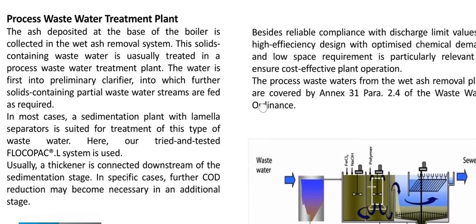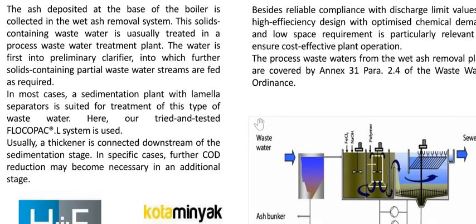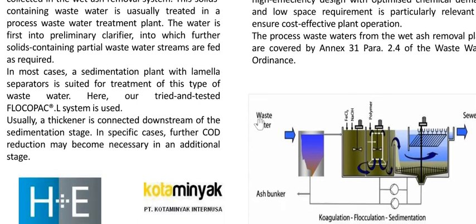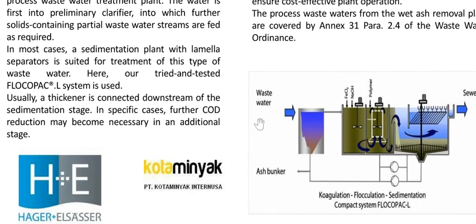Process wastewater treatment plant. The ash deposited at the base of the boiler is collected in the wet ash removal system. This solid-containing wastewater is usually treated in a process wastewater treatment plant. The water first goes into a preliminary clarifier, into which further solids-containing partial wastewater streams are fed as required. In most cases, a sedimentation plant with lamella separators is suited for treatment of this type of wastewater. Here, our tried and tested FLOCOPAC L system is used.